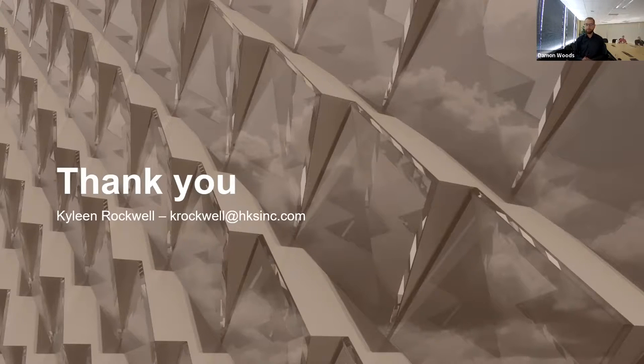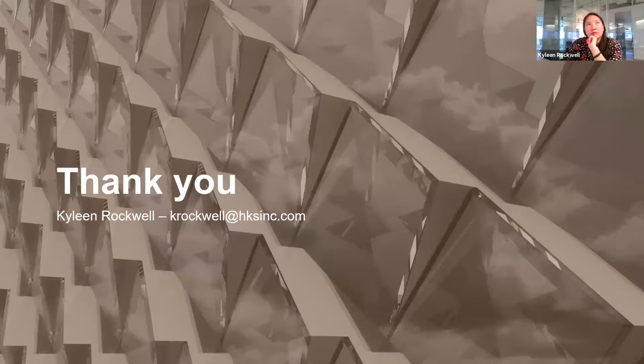Derek asks: with THERM being two-dimensional, what's the process for extrapolating or estimating a full 3D assembly? We haven't really done that — taking the 2D U-value and applying it in a three-dimensional assembly. Using the visualization you can create cool axon diagrams of a section up a wall with the thermal image and extrude it. But if you're thinking about a 3D assembly U-value, you'd have to break it down into two-dimensional plan and section ideas and do area-weighted U-values. With this workflow you could maybe start to automate that process, but I haven't gotten into that.